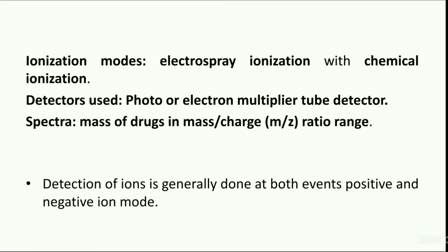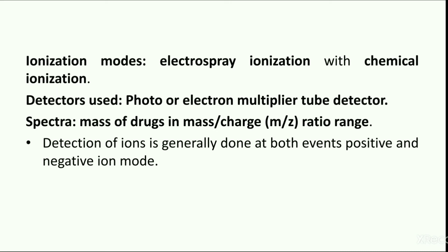After extraction, the eluate is either transferred online to the mass spectrometer or collected in a sample vial for further offline analysis. Analytes present in the eluate undergo ionization in the mass spectrometer; preferred ionization techniques include electrospray ionization and chemical ionization. Further, ions are accelerated through electric voltage and separated according to their mass-to-charge ratio, and finally detected through the detector. Detection of ions is generally done in both positive and negative ion modes.